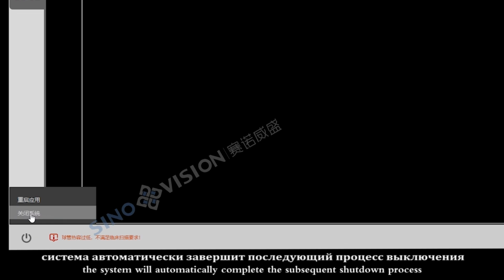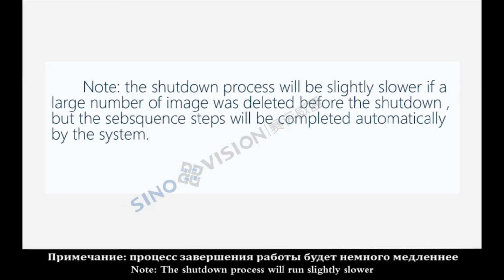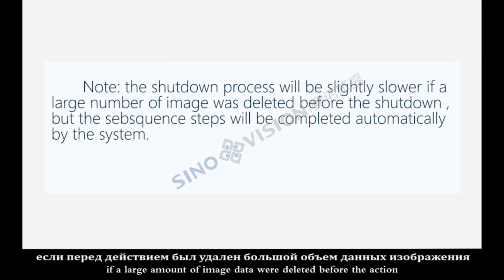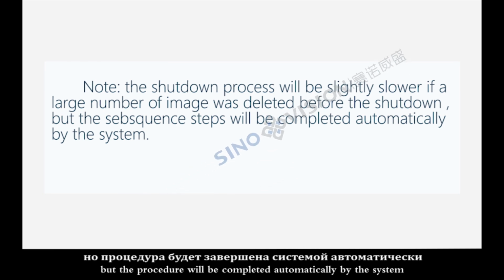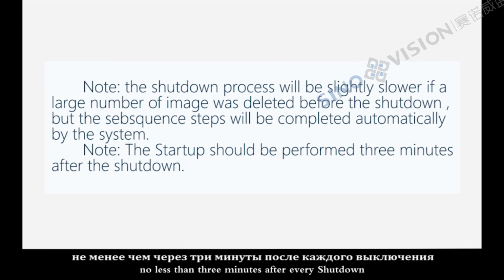The system will automatically complete the subsequent shutdown process. Note: the shutdown process will run slightly slower if a large amount of image data were deleted before the action. But the procedure will be completed automatically by the system. Note: the startup operation should be performed no less than 3 minutes after every shutdown.